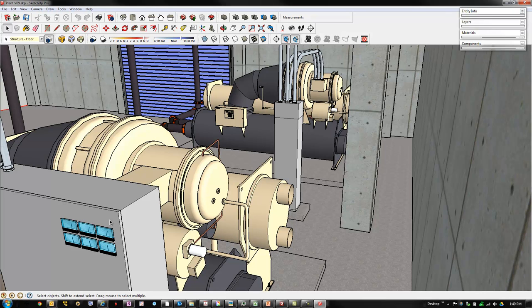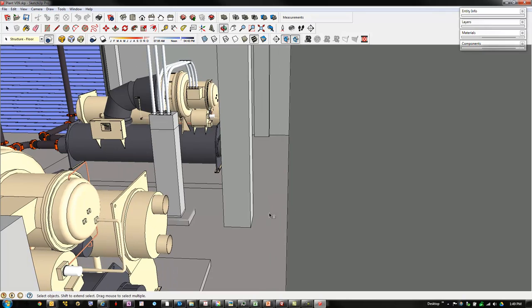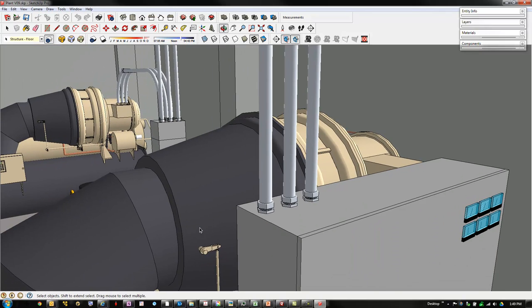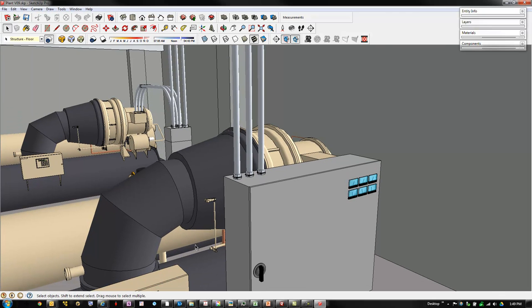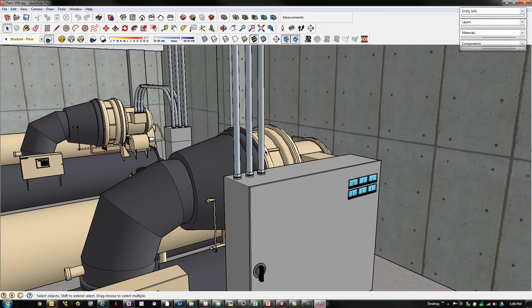So this has to be the compressor. You might be able to logically deduce that. It's making noise, it's got a motor attached to it, it's a centrifugal machine, and centrifugal machines have round impellers.